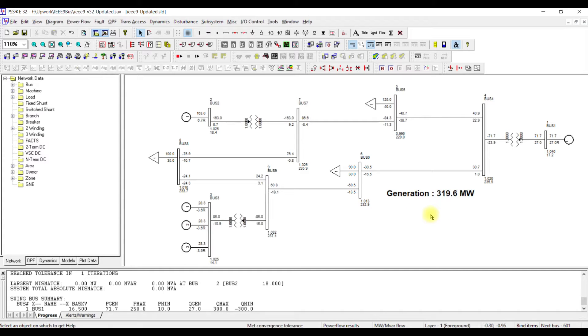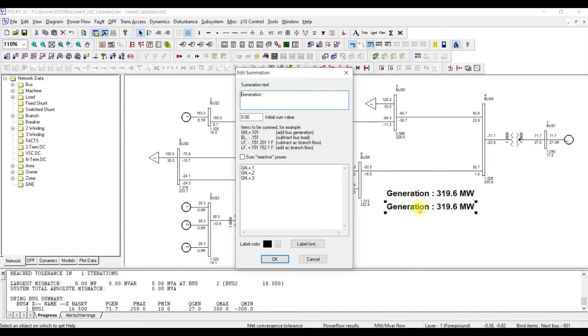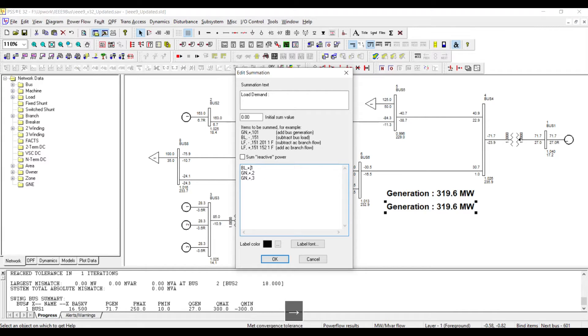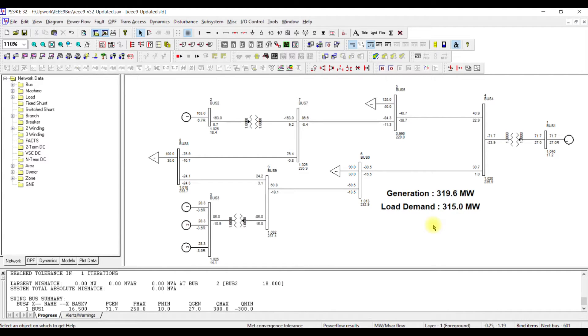To find the total load demand, copy and paste the summation function and change the attribute from generation to load demand. The syntax is BL (bus load), and bus loads are available at bus 5, bus 6, and bus 8. Selecting those three buses and pressing OK, we see the total load demand is 315 MW against a generation of 319.6 MW — meaning around 4 MW are system losses.